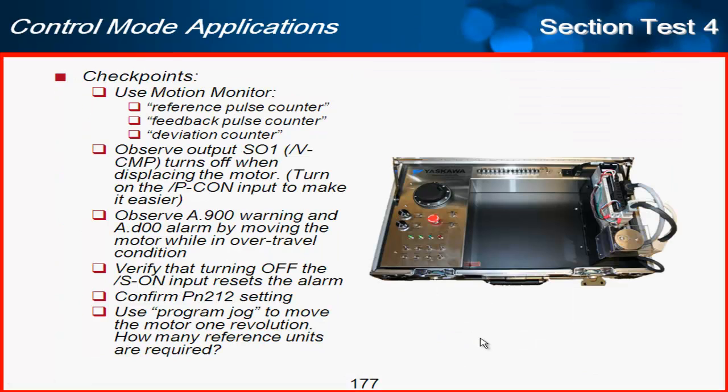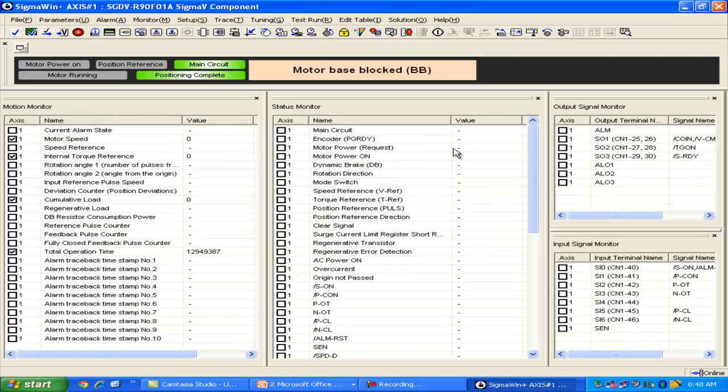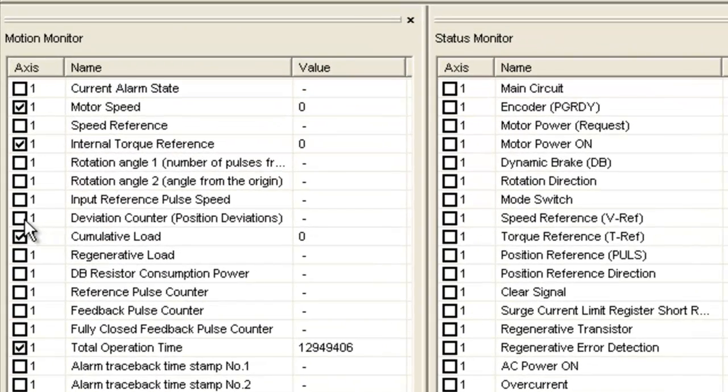So the first thing I can do here to check out this application is to use these monitors. Reference pulse, feedback and deviation. So let's go find those here. We've got the deviation counter, that's better described as the position error. There's the reference pulse counter, that's counting the pulses from the controller. And feedback is counting the encoder pulses, feedback from the motor.